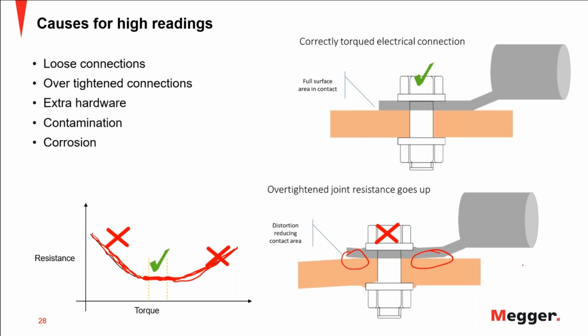Also, you could have some extra hardware. Let's say somebody used a washer here. This is where I was saying, if you torque this to the spec, the torque value is going to be good. But what if you have something in between the two surfaces that you want to make the connection with? That is going to increase your resistance there. Corrosion, after some aging of the connection, you could have some corrosion there.